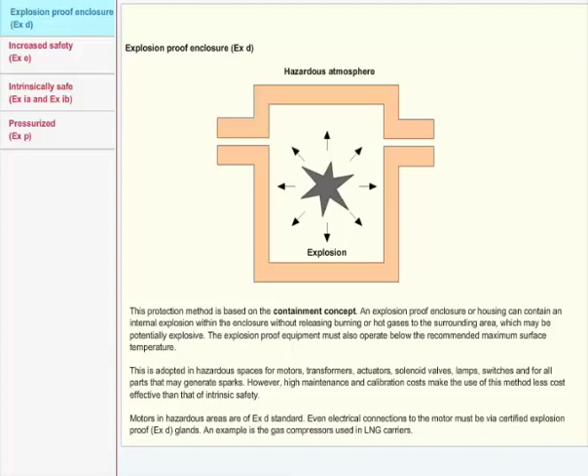This is adopted in hazardous spaces for motors, transformers, actuators, solenoid valves, lamps, switches, and for all parts that may generate sparks. However, high maintenance and calibration costs make the use of this method less cost-effective than that of intrinsic safety. Motors in hazardous areas are of Ex d standard. Even electrical connections to the motor must be via certified explosion-proof Ex d glands. An example is the gas compressors used in LNG carriers.